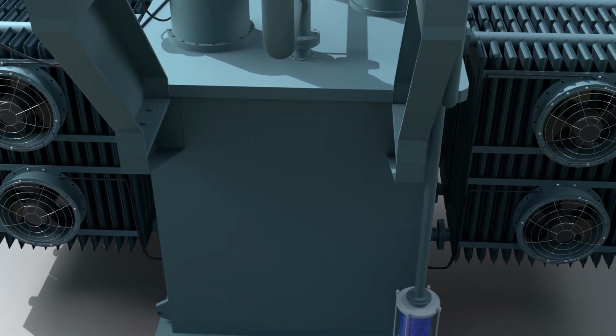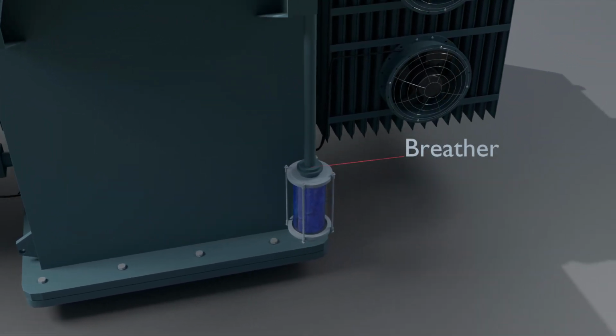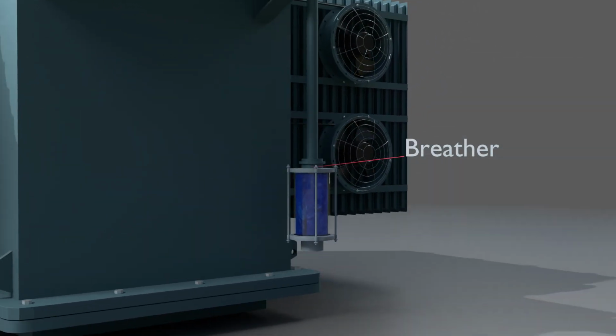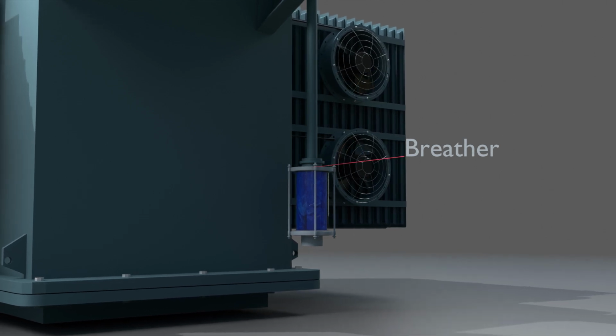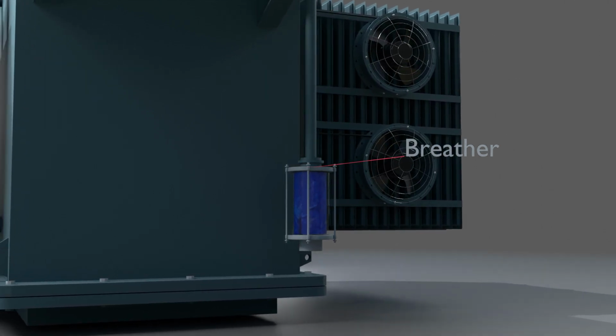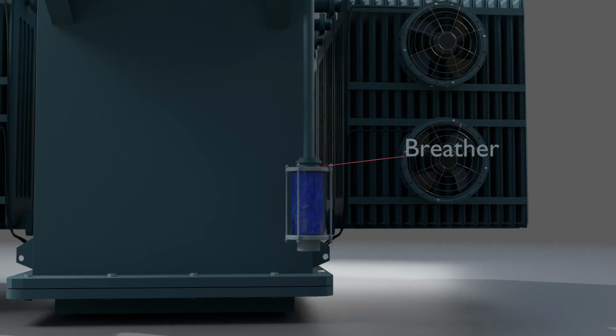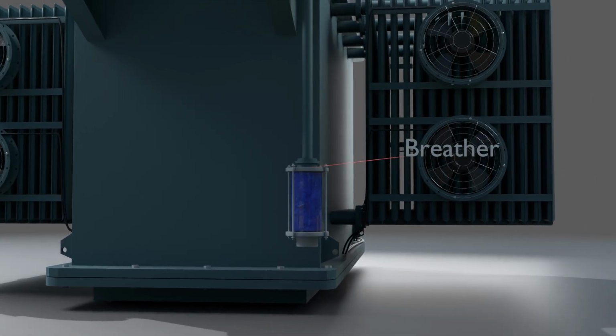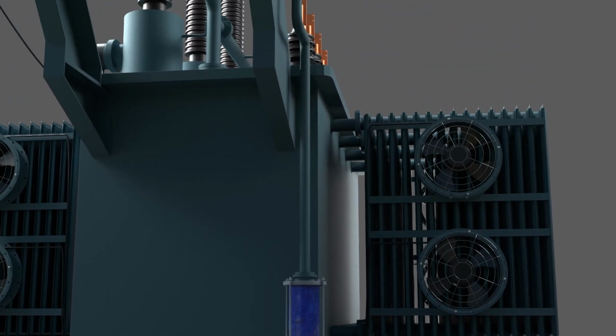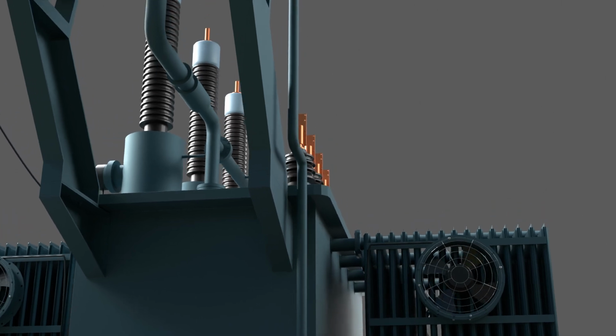Reserving oil in the transformer tank matters, with the conservator keeping it full as heat changes. Then there's the breather. It stops moisture from getting into the transformer oil. As the transformer cools, air flows through the breather, where silica gel grabs the moisture, letting only dry air into the system. This keeps the oil and insulation safe from damage.